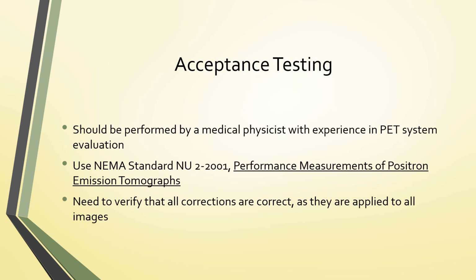The first step in ensuring image quality is acceptance testing. This is performed whenever a new camera is installed or purchased, and it should be done before use. This is performed by a medical physicist with experience in PET system evaluation, and it must adhere to the performance measurements of positron emission tomographs. And there is a need to verify that all the corrections are correct, as they will be applied to all of the images.